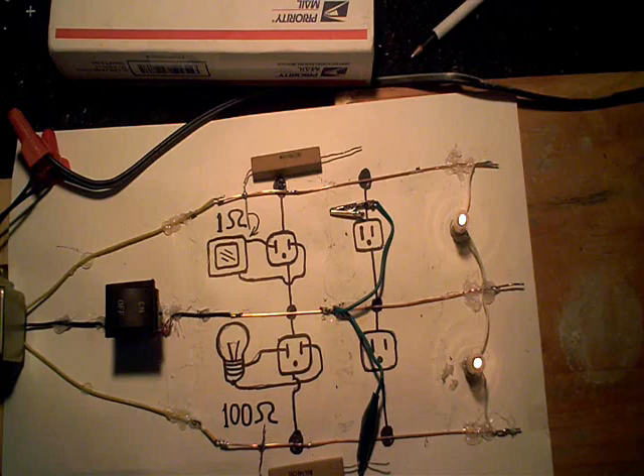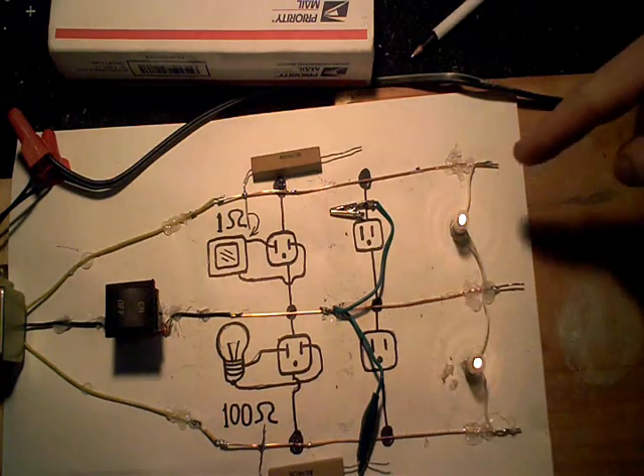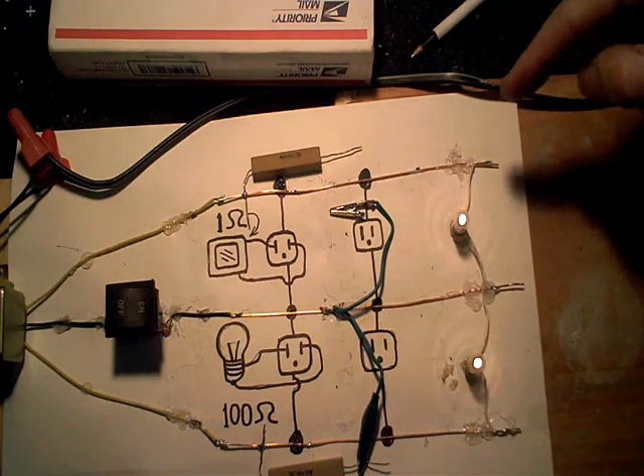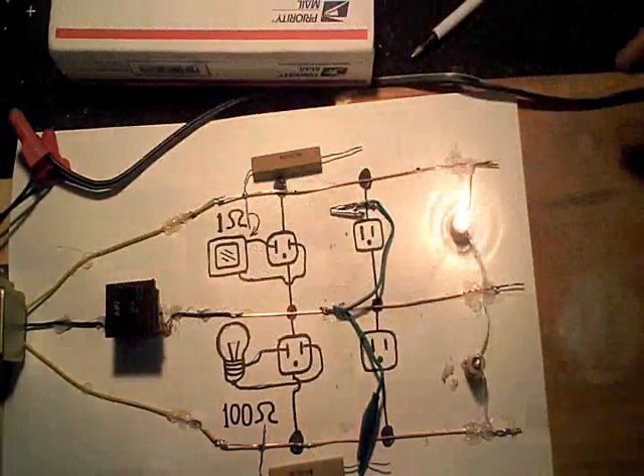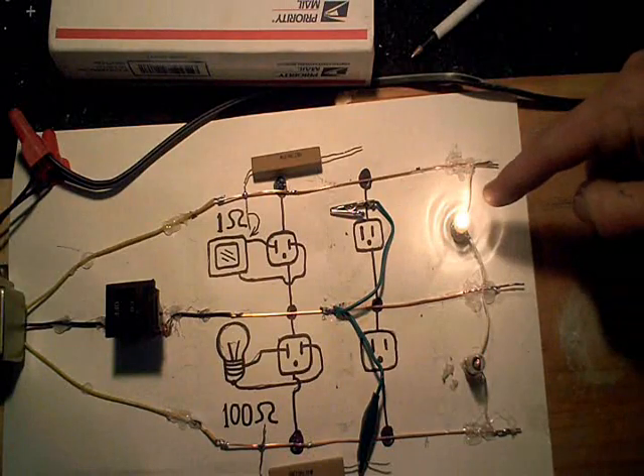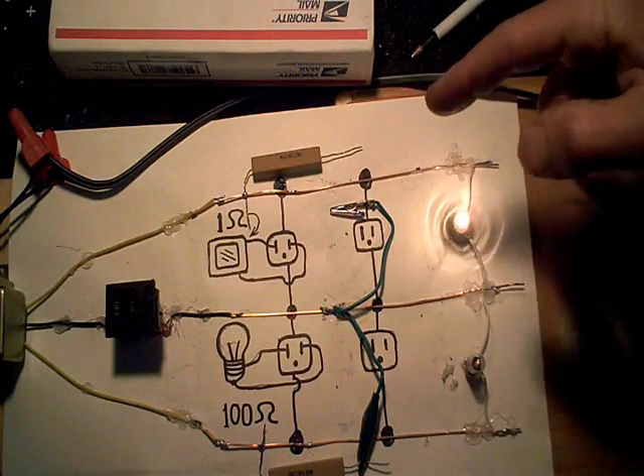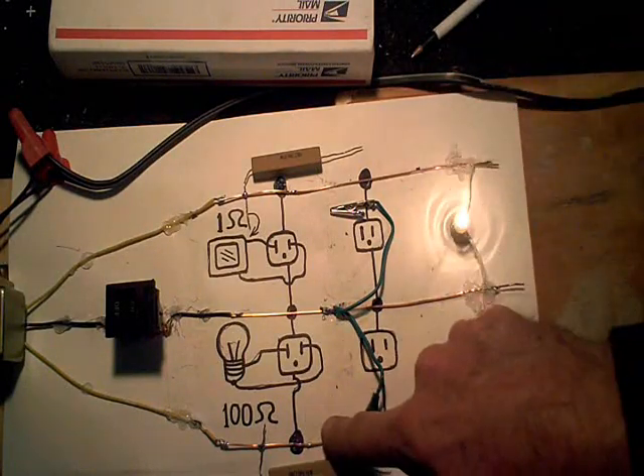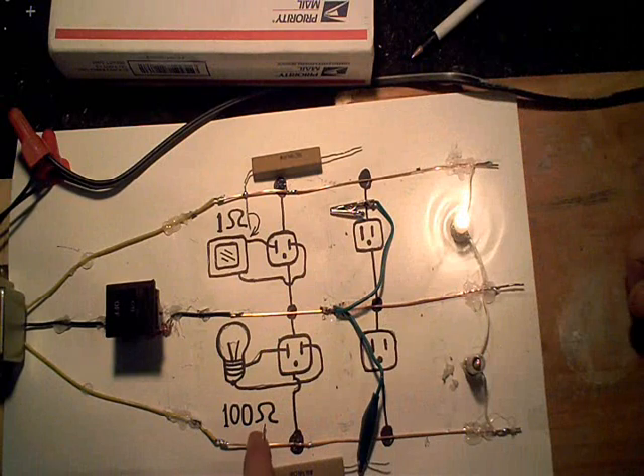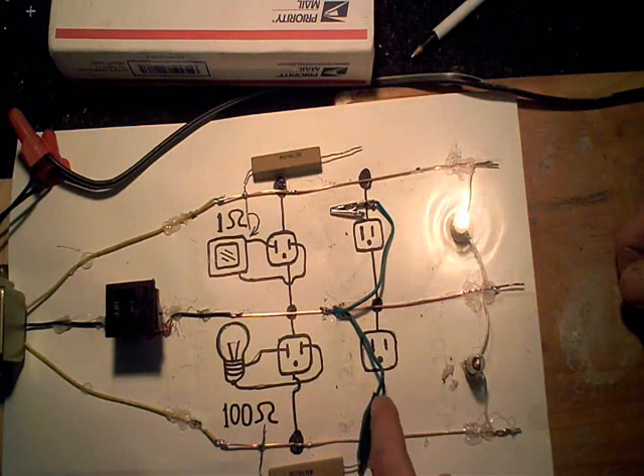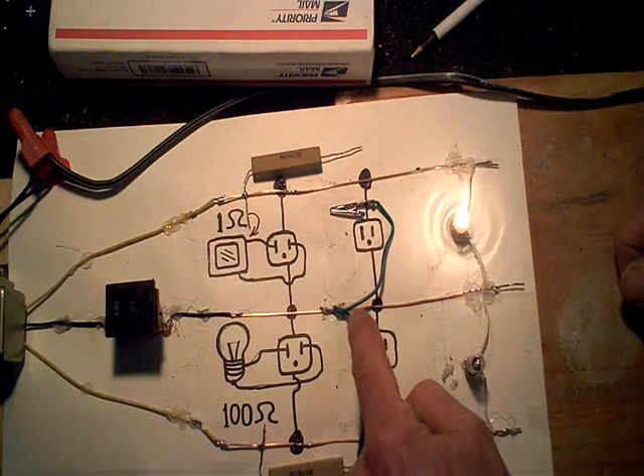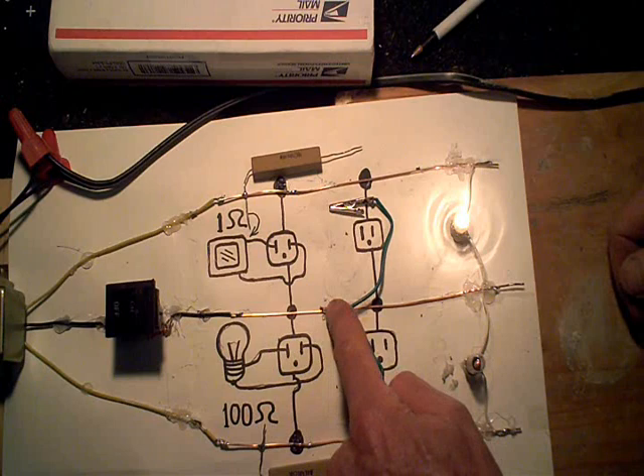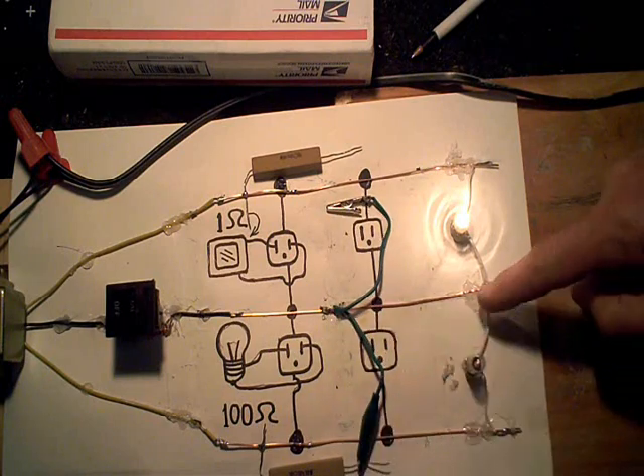I find that really interesting. Anyway, you can understand how it is the higher voltage goes to the lamp here. If you follow the current path, we know that the 220 would be from here to here. And in this case, it's going through the resistor, and it's going right across to the center neutral wire, which is now broken.